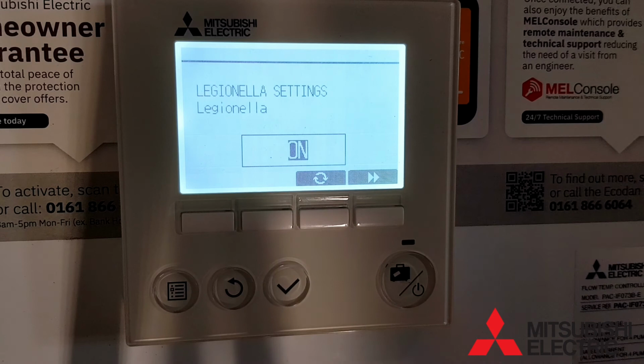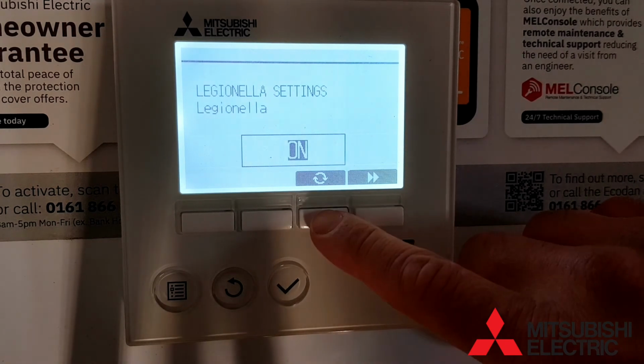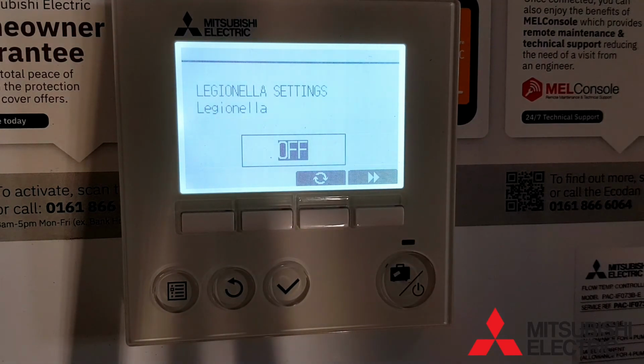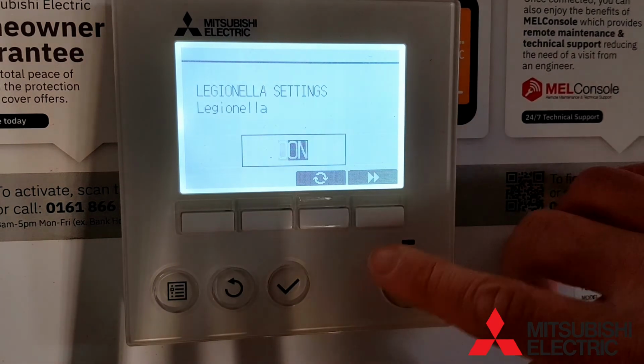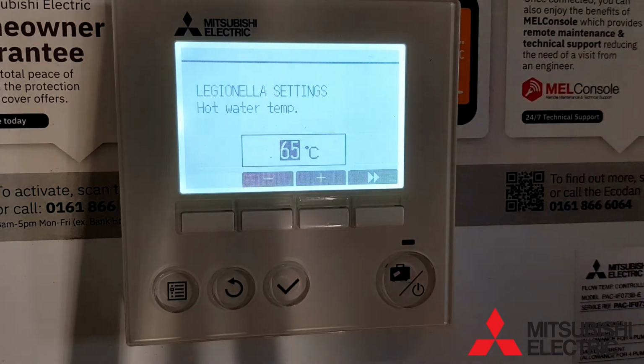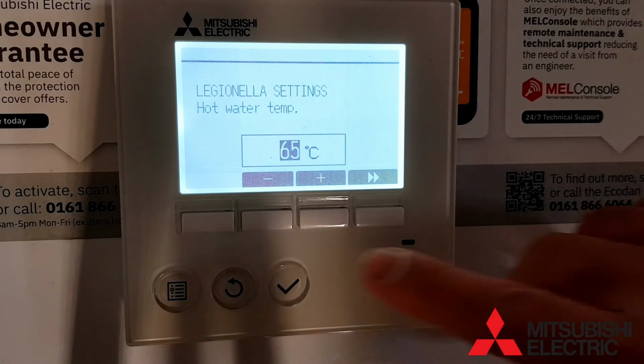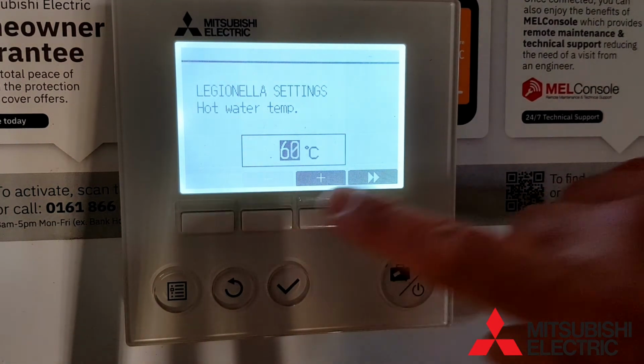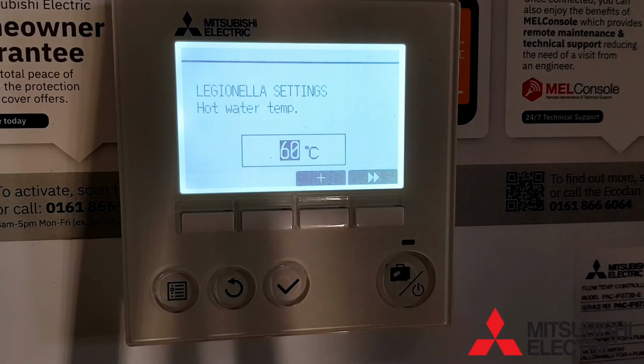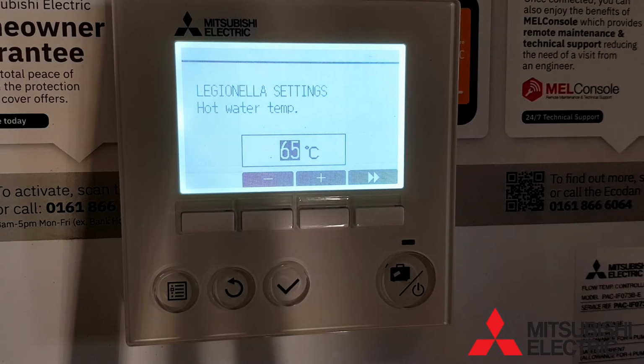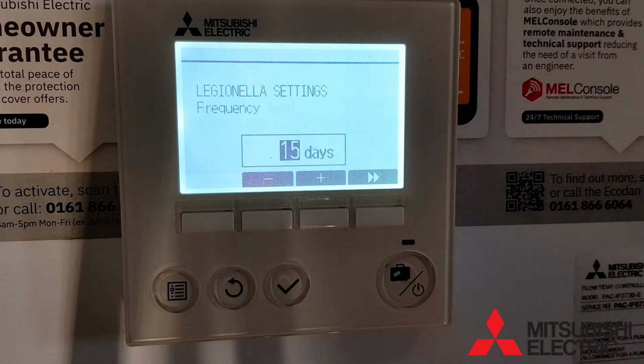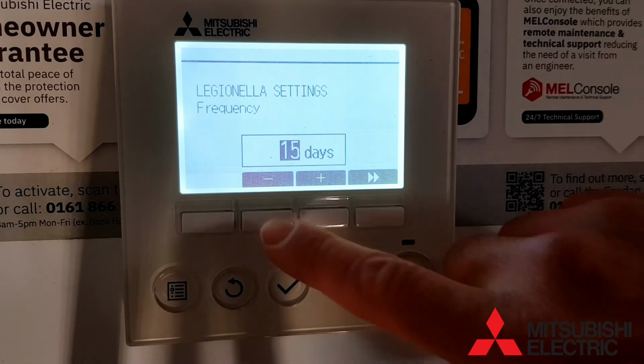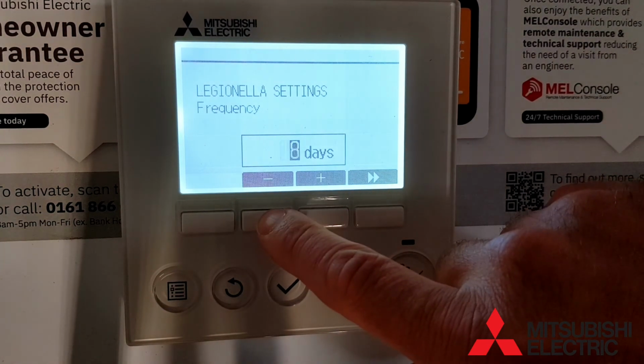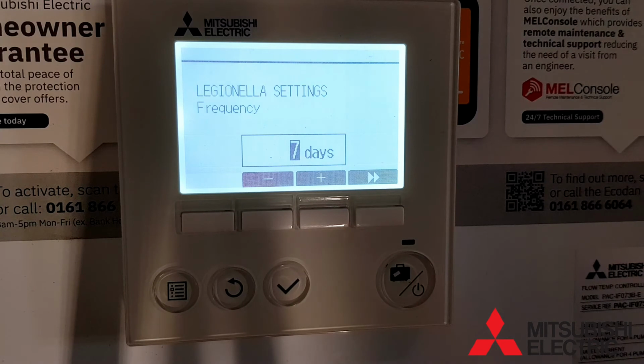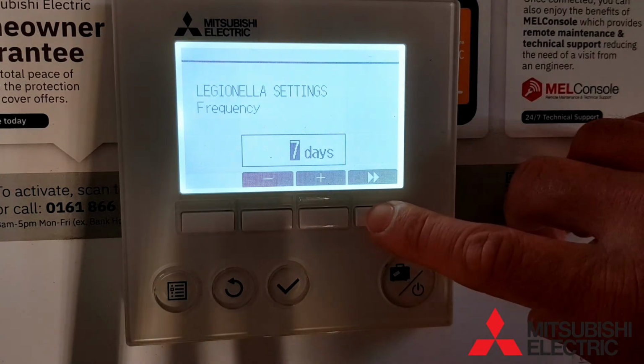We now move on to the Legionella settings. The first one is simply selecting whether you have the Legionnaire's function on or off. You now need to set your Legionella target temperature. 60 degrees is sufficient for Legionnaire's prevention, so anywhere from 60 to 65 degrees is absolutely fine. Next, we have the Legionella cycle frequency, how often you want it to operate in Legionnaire's mode. Every 7 days is absolutely fine to meet building regulations. This is the most common setting.